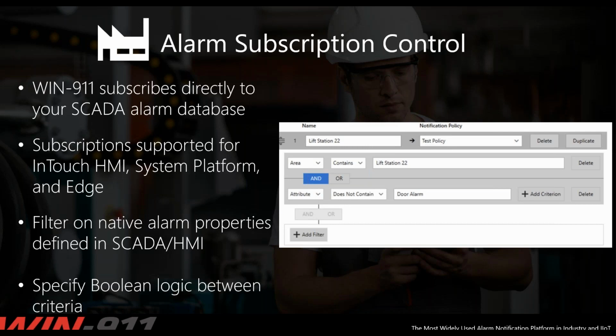And these subscriptions are supported for InTouch HMI, System Platform, and Edge. You can filter the native alarm properties defined in the SCADA and HMI. And as you can see, it's highlighted in blue. That's the And/Or feature, which is the Boolean logic. And this allows for much more flexible and customizable filtering when you're determining what alarms are going to come in and then how they need to be grouped.